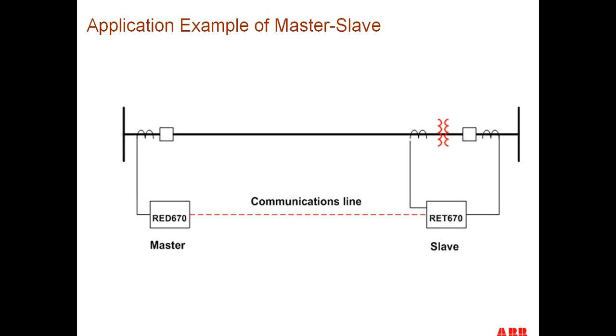Which is the percentage of use between distance protection and differential protection? Wow, that's a good question. I would say the predominant number of relays used in this country to date have been distance relays. Most of those distance relays were used over power line carrier, which really doesn't lend itself to line current differential relays because the bandwidth isn't great enough. But with more people using fibers now and depending less on power line carrier, you'll see that line current differential relay use will increase manyfold because of the availability of the communications channel.